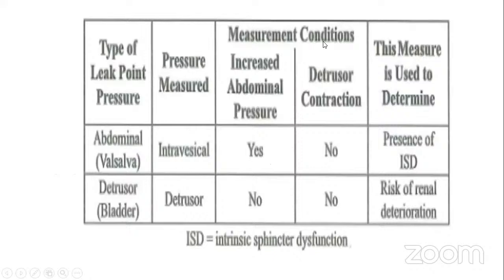This is the measurement condition. This is a type of leak point pressure: abdominal or Valsalva, and detrusor or bladder leak point pressure. This is a pressure measurement, intravesical, and this is the detrusor pressure. With an increase in abdominal pressure, in Valsalva, there is no increase in detrusor contraction. This measure is used to determine the presence of ISD. The detrusor or bladder leak point pressure measures the detrusor pressure, where there is no increase in abdominal pressure and no increase in detrusor pressures, for the risk of renal deterioration secondary to this.